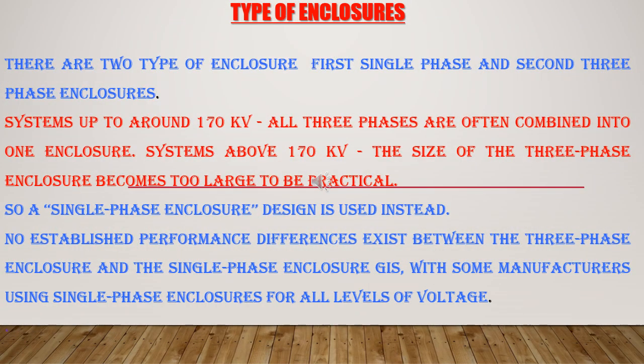There are two types of enclosure: first single-phase and second three-phase enclosures. In systems up to around 170 kV, all three phases are often combined into one enclosure. In systems above 170 kV, the size of the three-phase enclosure becomes too large to be practical. So a single-phase enclosure design is used instead. No established performance differences exist between the three-phase enclosure and the single-phase enclosure GIS, with some manufacturers using single-phase enclosures for all levels of voltage.